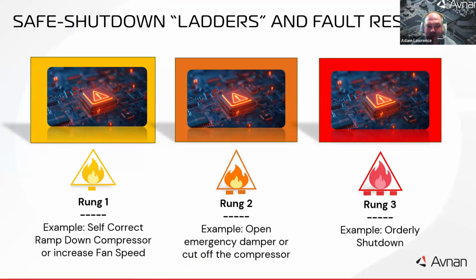To manage those varying fault levels consistently, we use the concept of a safe shutdown ladder, which is basically a hierarchical sequence of actions the controller will take as a fault condition escalates. For example, imagine the condenser coil temperature is climbing too high. At the first sign of overheat, the controller might take a mild corrective action, like ramping down the compressor or increasing the fan speed. That's rung 1 of the ladder, trying to self-correct. If the temperature keeps rising, the fault condition worsens, rung 2 might open an emergency damper or cut off the compressor for short intervals. And if it becomes a severe overheat, indicating a potentially dangerous condition, rung 3 is an orderly shutdown of the system.